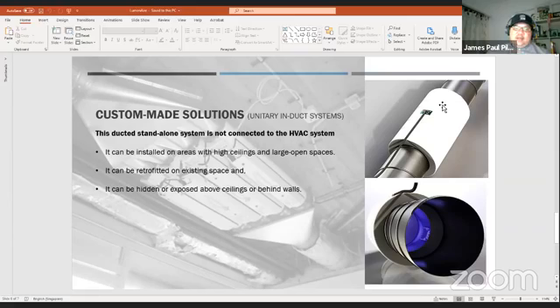Why is that type of UVGI not effective enough? It's because of the exposure time. Once you integrate it with the HVAC system, the CFM makes the air move so fast that it's just a millisecond when it passes through the UVC. It passes too quickly to kill the bacteria, since there's a certain exposure time needed for bacteria and viruses to be disabled.